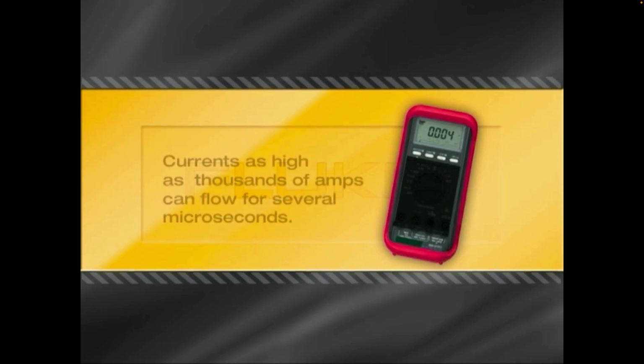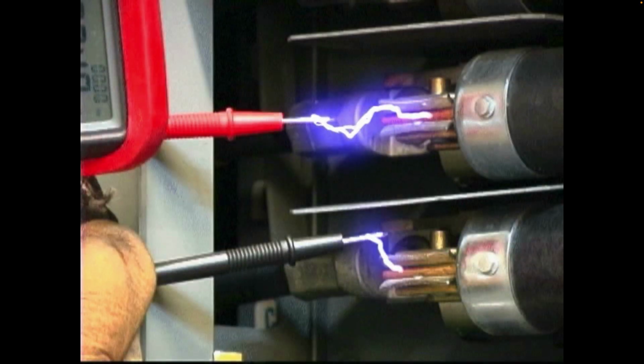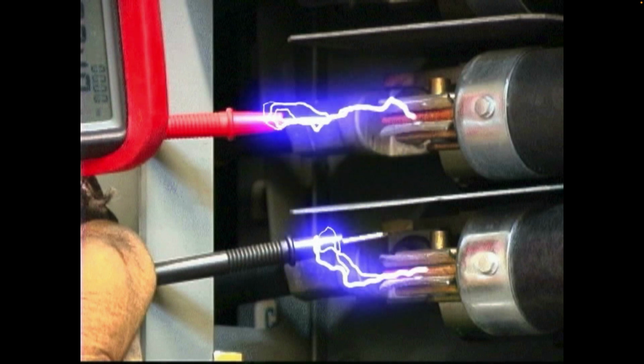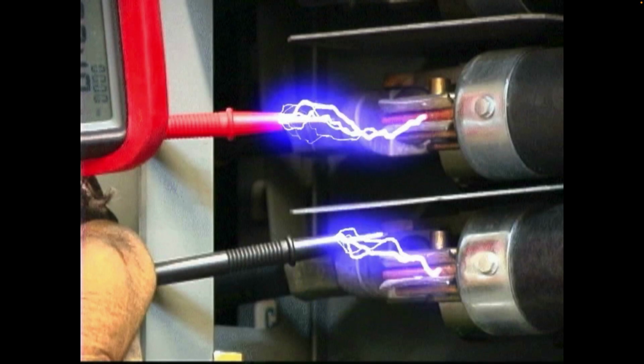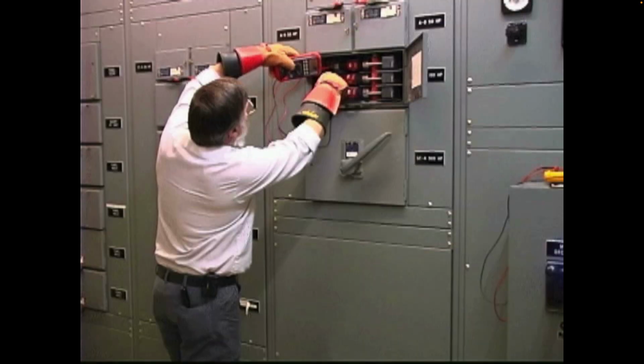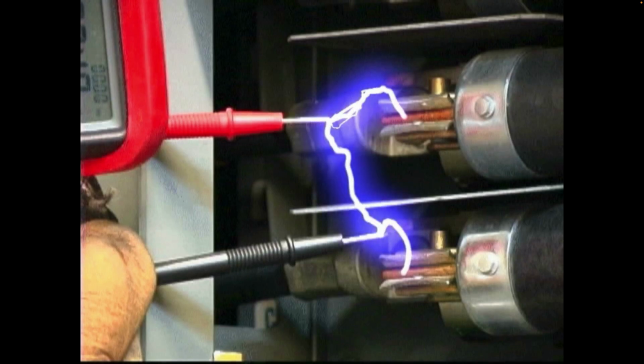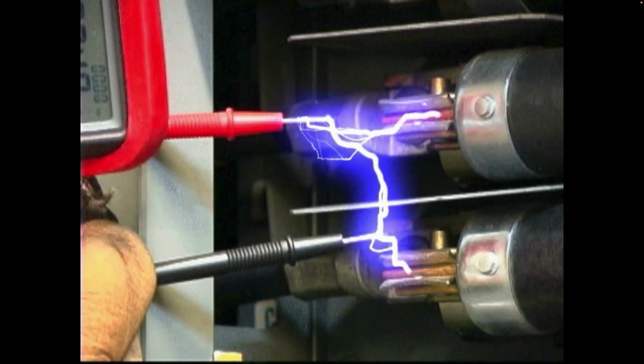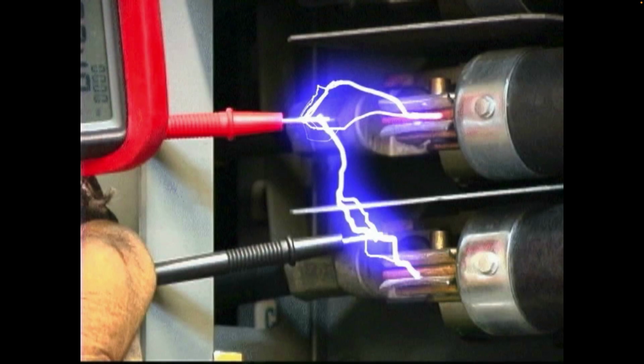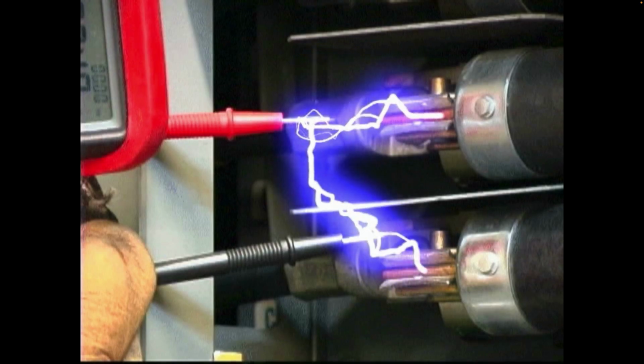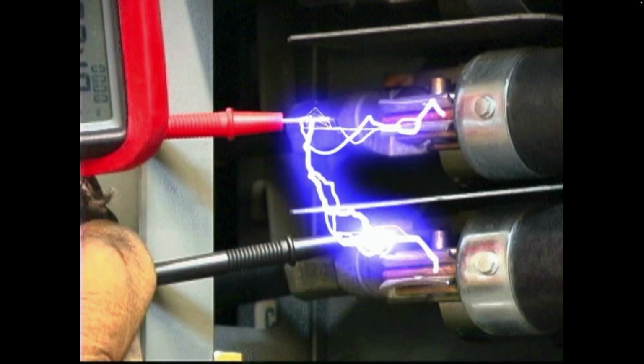Short-circuit currents as high as thousands of amps can flow for several microseconds. At these current levels, the tips of test leads superheat, and the handheld probe tips start to burn away, drawing an arc from the contact point to the probe tip. The tech sees a bright blue arc flash, and at the same time is startled by the bang of the arc exploding inside the meter. The arcs follow the vaporized test probes. If these two arcs join through close proximity of exposed metal from the test probes or other mechanisms, one large arc is formed, providing a low impedance path directly from one electrical phase to another.